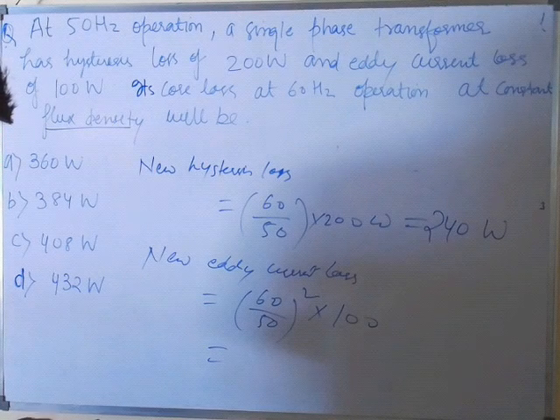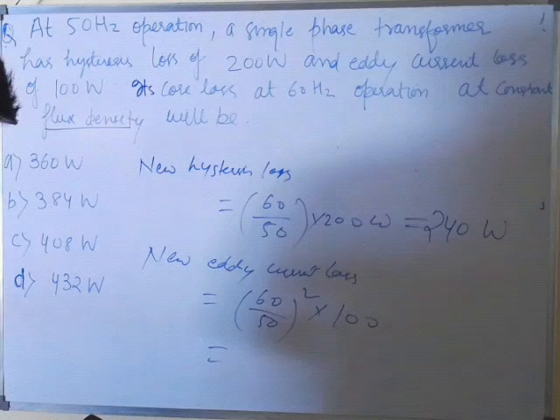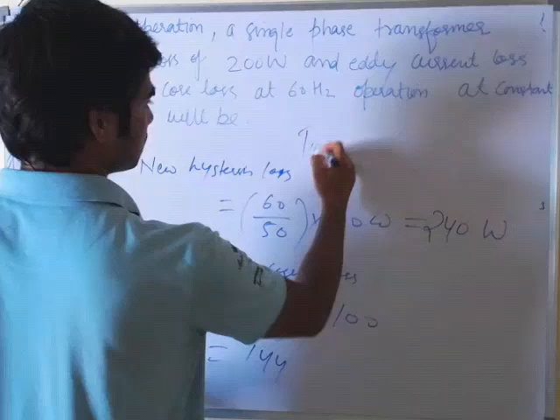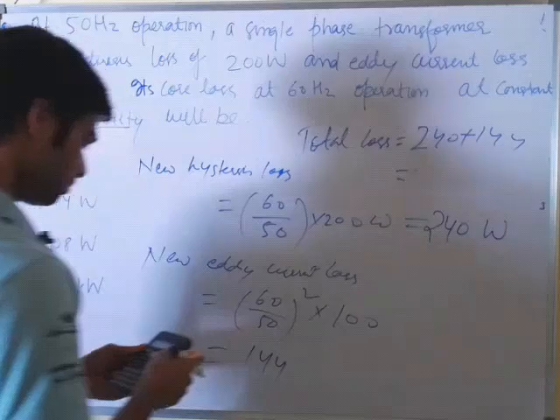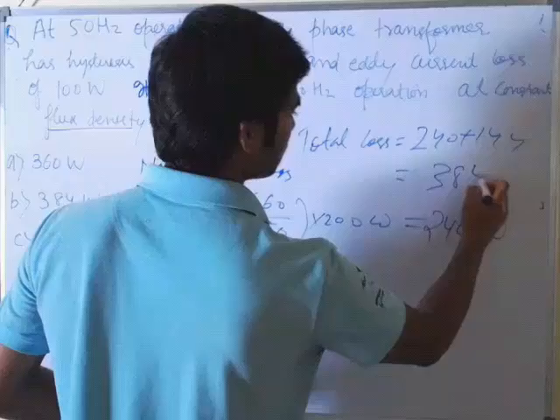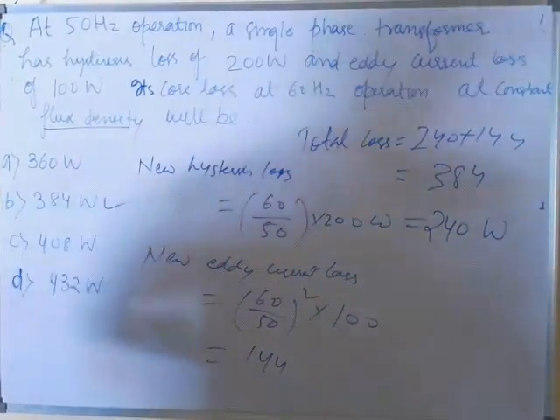The new eddy current loss is (60 ÷ 50)² × 100, which equals 144 watt. The total core loss is 240 plus 144, which equals 384 watt. So the answer is option B.